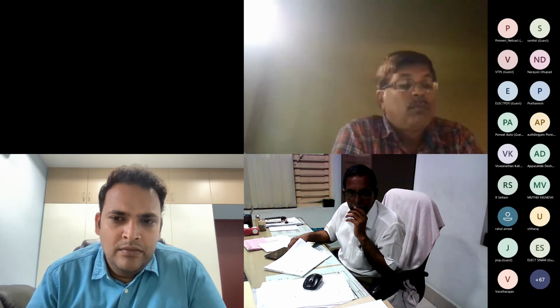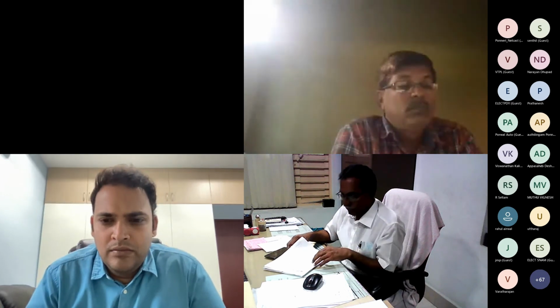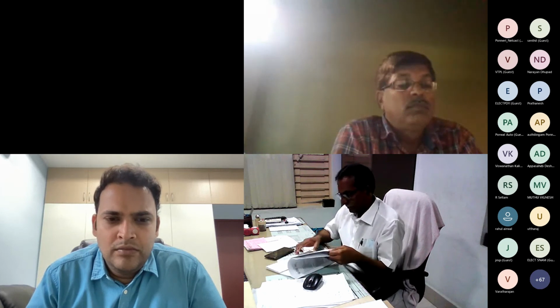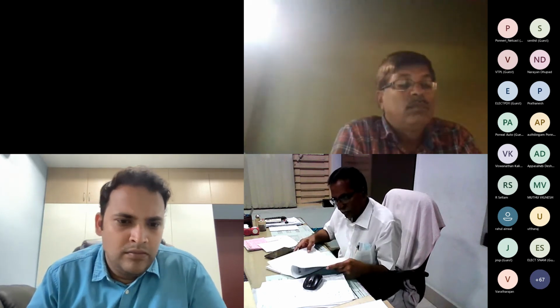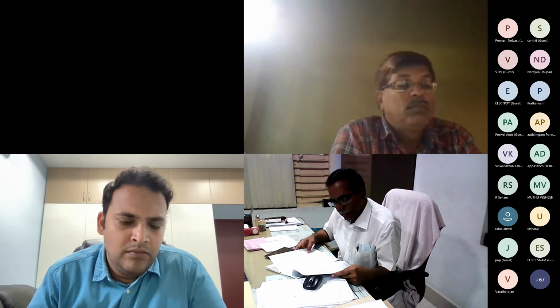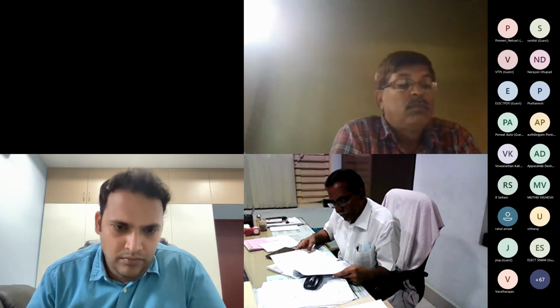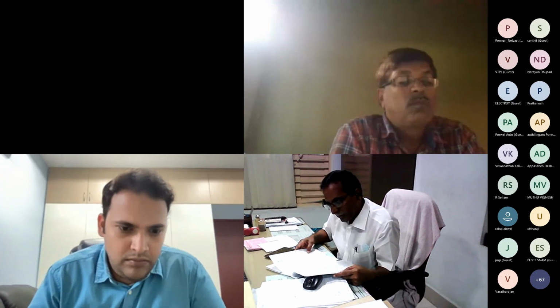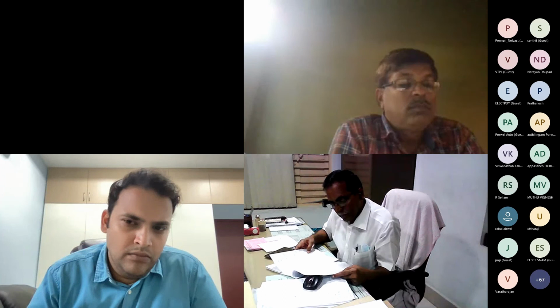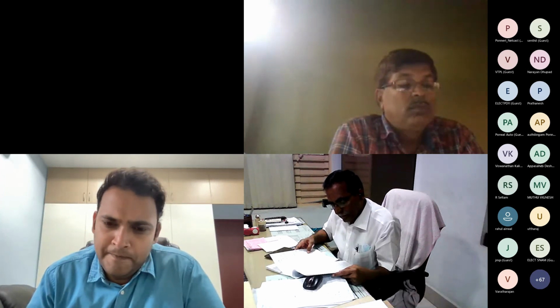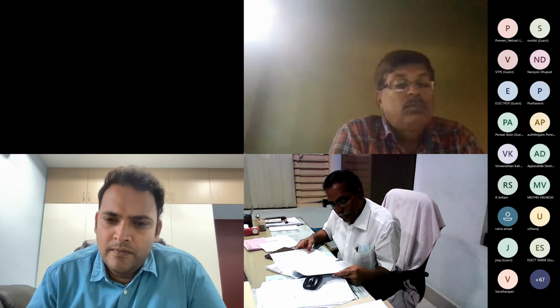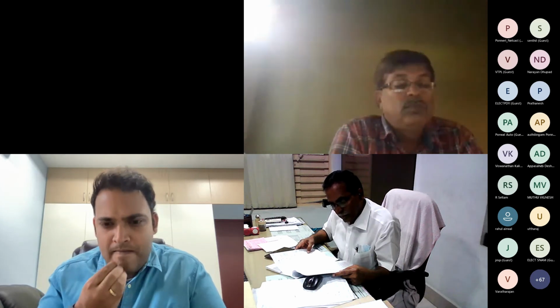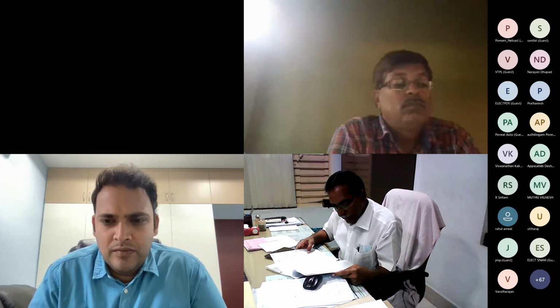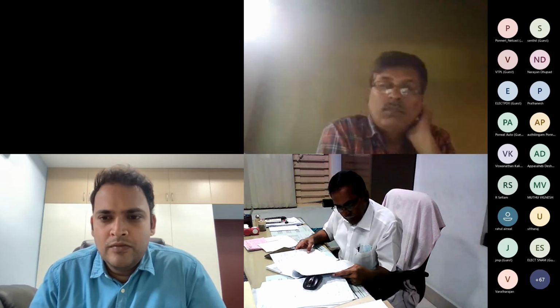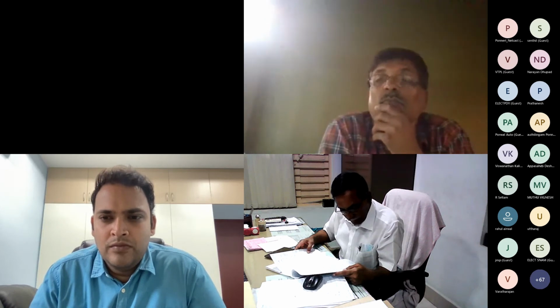So for the human intervention, what they used to do is fix some demand controller. Whenever they come near that kVA, it buzzes, alarming the operator to reduce the power. But it is a continuous process, and it is a very alerting process for the operators, and very tedious also. It is not recommendable. So what we are talking about is that there are many PLC controllers available from many manufacturers in the market. The PLC controller takes complete control of your maximum demand, sharing the power among your auxiliaries as well as the furnaces.